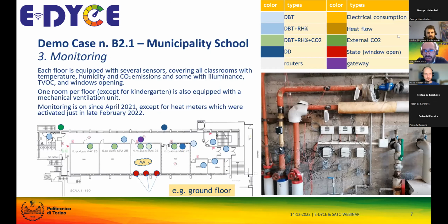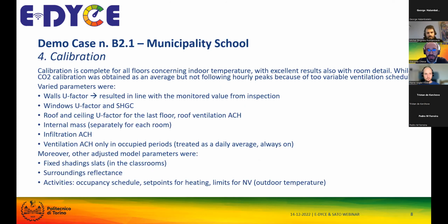In the school, which is very large, we have also installed a more complicated heat and electrical consumption solution. We have heat flow meters installed in all cases for heating consumption. As Pierre said, and also Tristan, this is not easy to install because we need to cut the tube, so it has to be done when it's not the heating season. We also have one external CO2 probe, some illuminance probes, and some total VOC probes. The window state sensor with battery is not the best solution, because the battery needs to be changed too often to be cost-effective in terms of replicability.